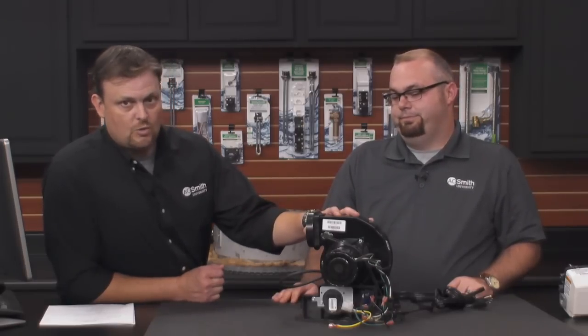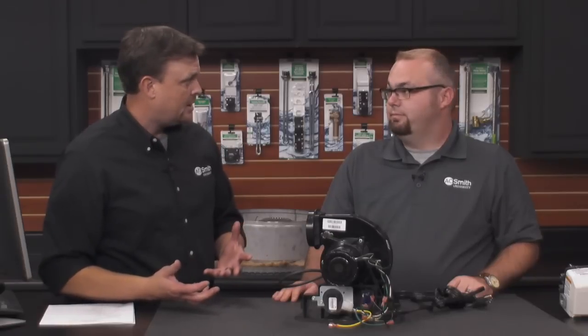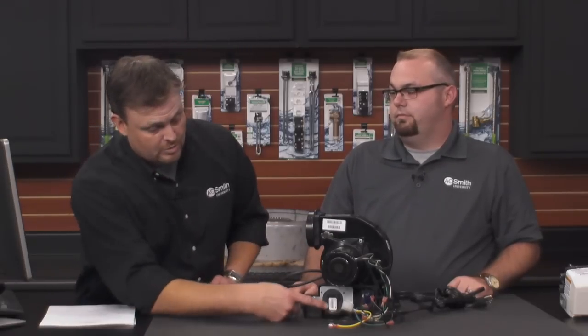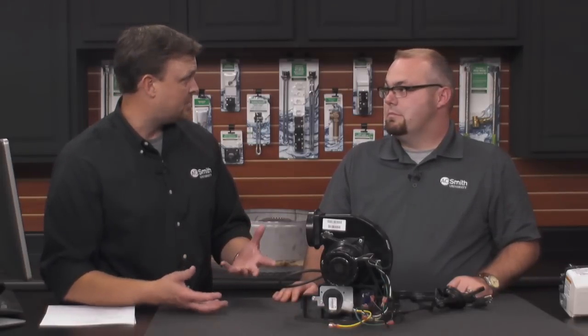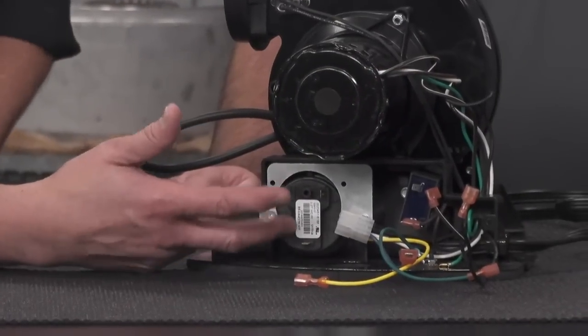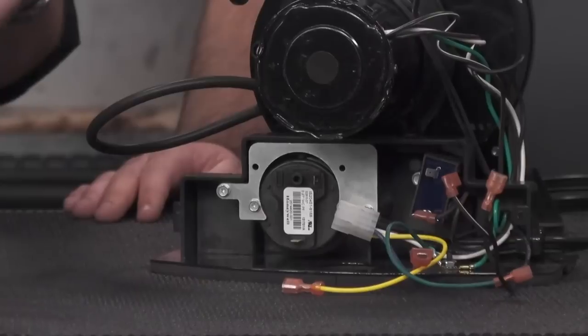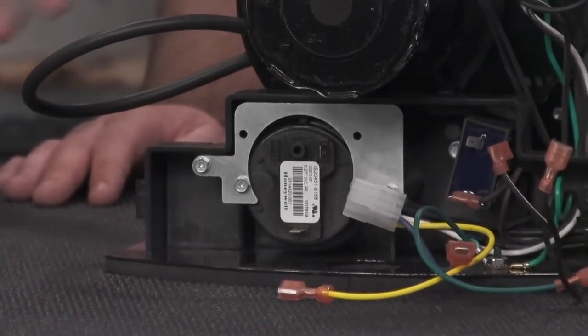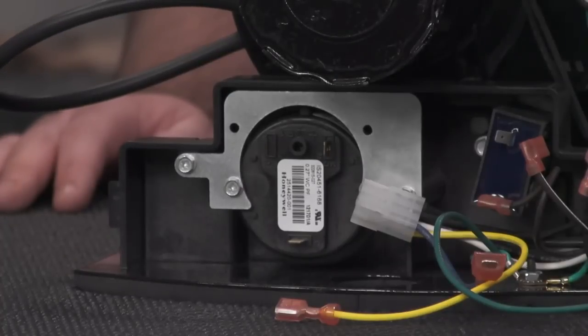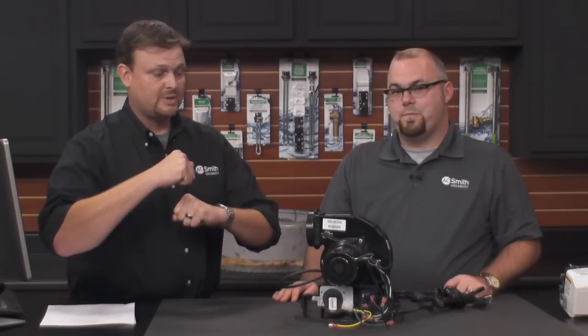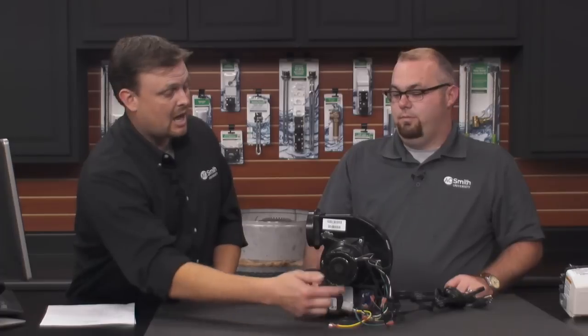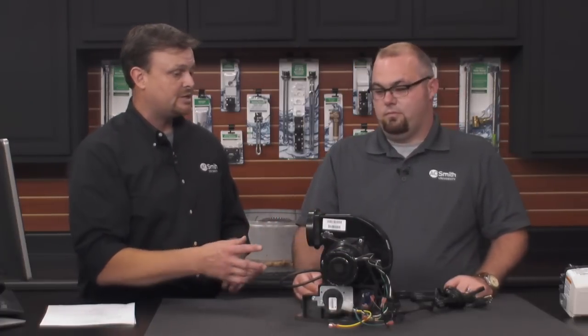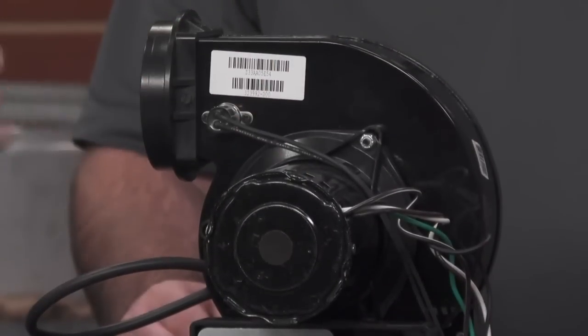Okay, and this is a normal blower. We still use a blower prover switch. It's a normally open switch that closes on a rise or a drop in pressure, whichever the switch is designed for, to prove that the blower is running. Those contacts sitting in there are open. When the blower kicks on, the pressure from the blower closes those contacts and allows electricity to pass through. In line with that you still have a high vent temperature switch. The reason I'm mentioning that is that the switch activation point is a lot lower than it was on the older style.